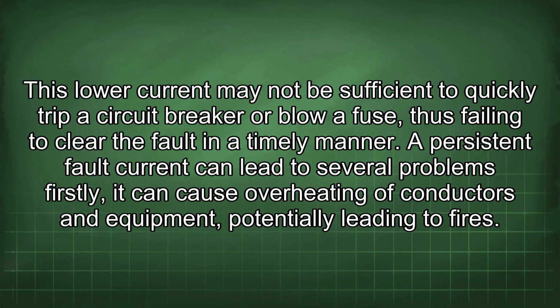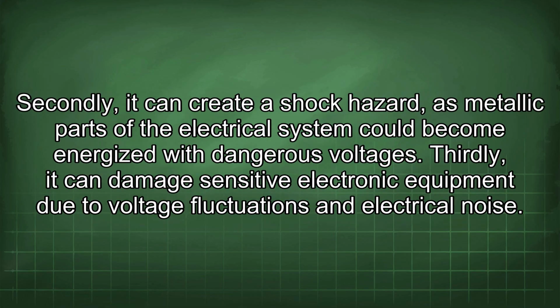A persistent fault current can lead to several problems. Firstly, it can cause overheating of conductors and equipment, potentially leading to fires. Secondly, it can create a shock hazard, as metallic parts of the electrical system could become energized with dangerous voltages. Thirdly, it can damage sensitive electronic equipment due to voltage fluctuations and electrical noise.